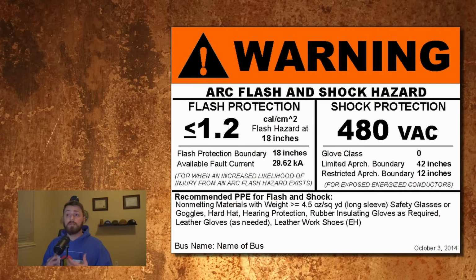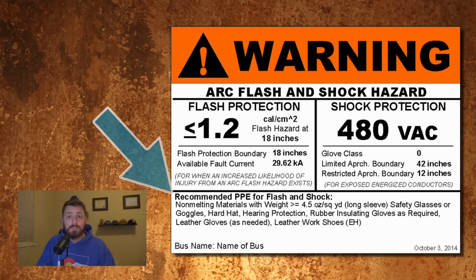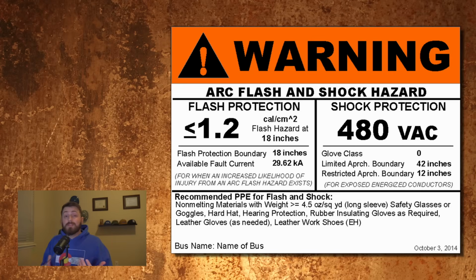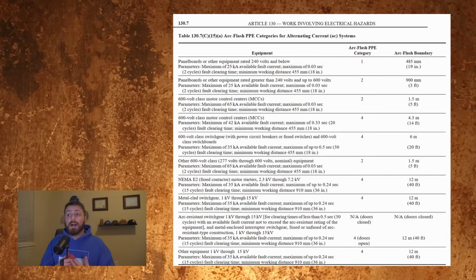Some job sites will have accurate, up-to-date arc flash studies with stickers on each individual piece of gear that tell you what PPE you need to don for a certain task or working on a certain piece of equipment. Knowing my audience, many of y'all aren't so lucky. The alternative to selecting PPE based off an arc flash study sticker on the gear is using what's called the table method. So NFPA table 130.7, or if you're in Canada, CSA Z462, they have a bunch of tables that help you pick the PPE required for your task.